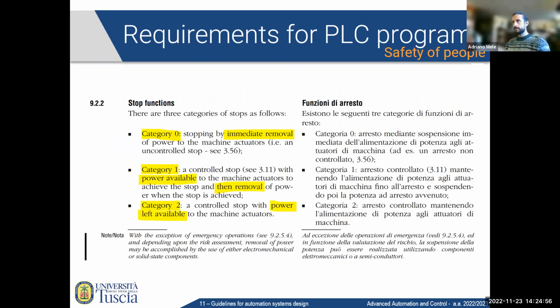So stop functions, here it is. These are the emergency stop functions that we were talking about before. So you see that category 0 is stopping by immediate removal of power to the machine actuators. Just an uncontrolled stop. This is basically for the safety critical things. You just disconnect everything and everything stops. Category 1 is a controlled stop. So the power is still available to the machine actuators to achieve the stop, and then all the power is removed when the stop is achieved.